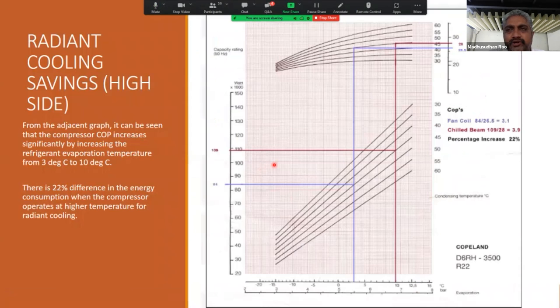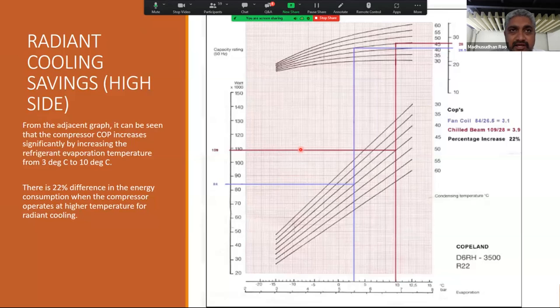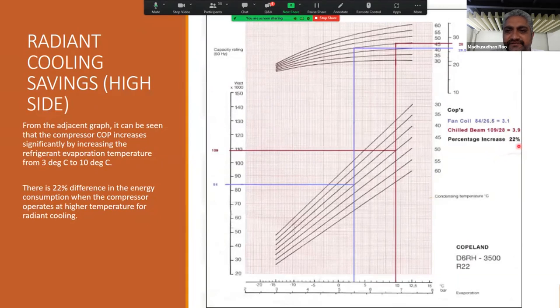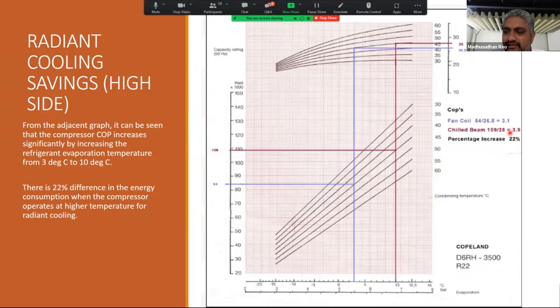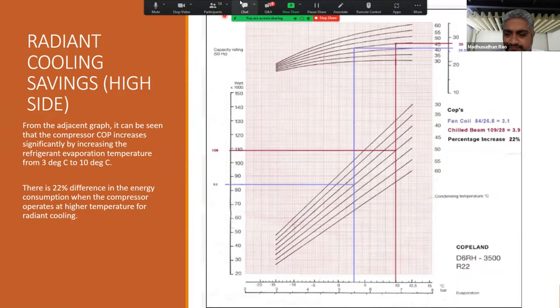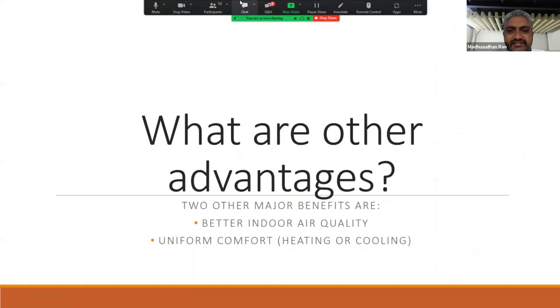So when you look at the difference in the COP of the chiller, because now you are supplying 16 degrees centigrade instead of say 7 degrees centigrade, there's at least about 20 to 25% difference in that. So combined with this and the fan motor energy savings that you get, you could safely say that you could get about 30% savings, 5% here and there, with radiant cooling. So apart from the energy savings, there are a couple of other advantages that I want to talk about.